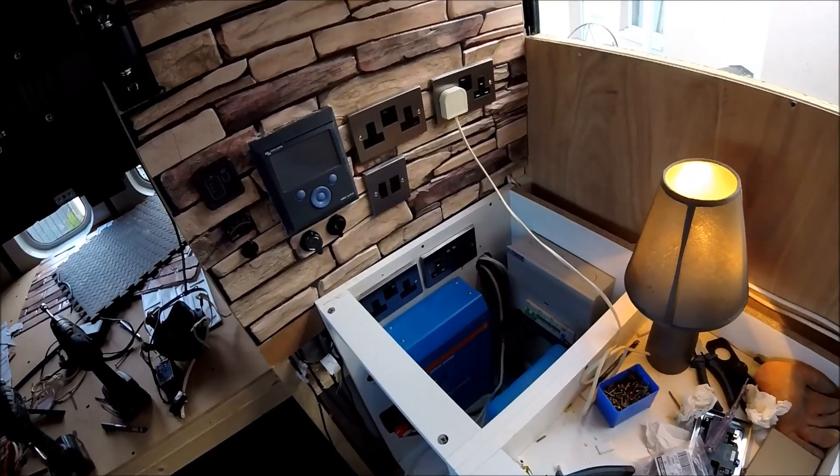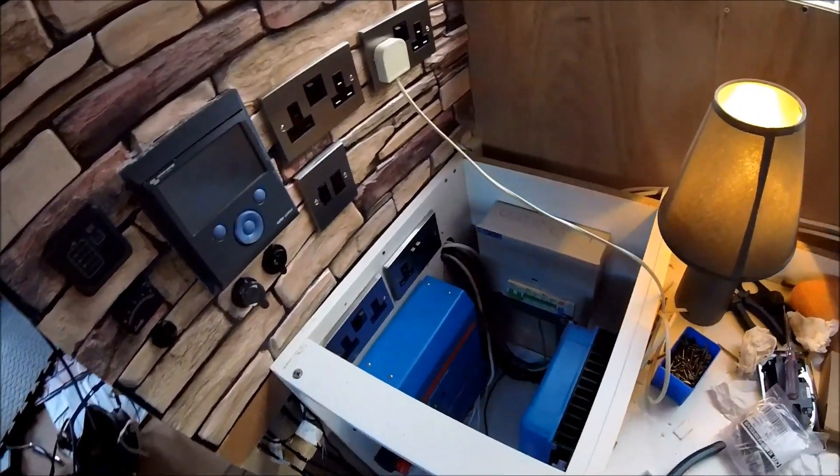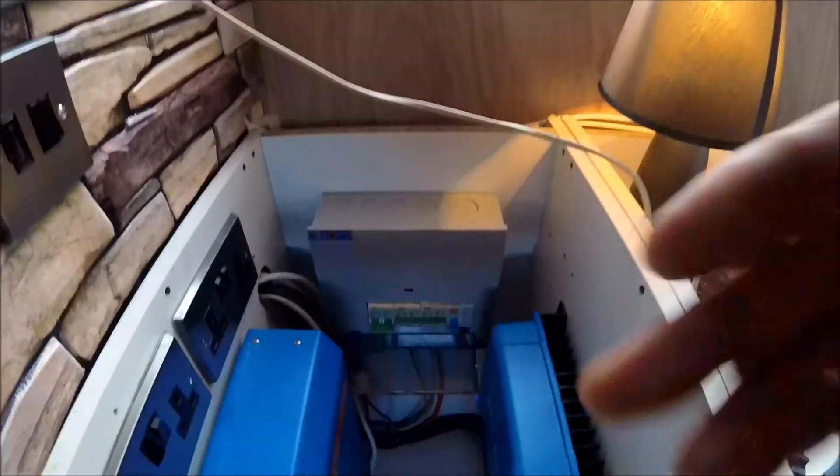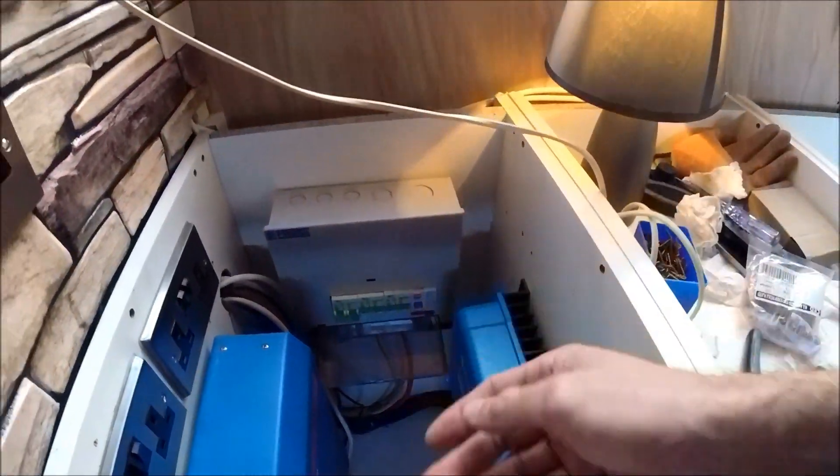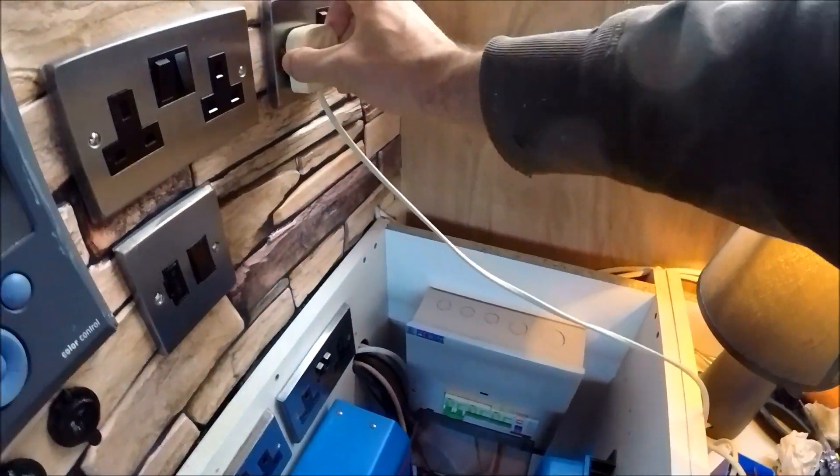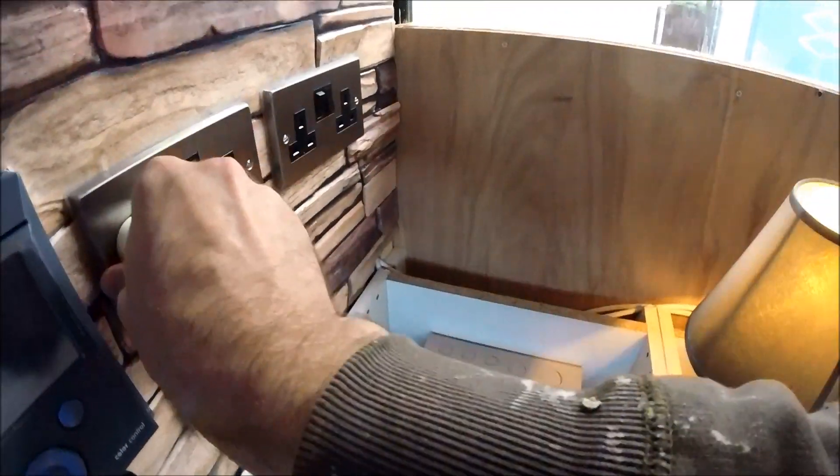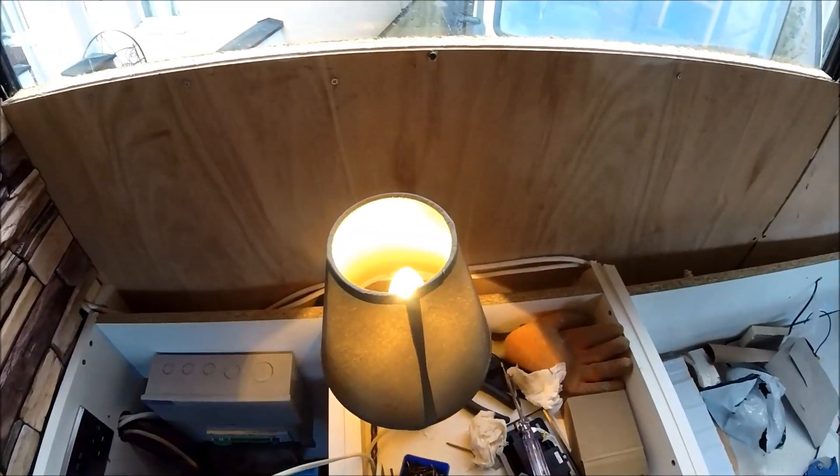Just reset the RCD and plug it back in onto the hookup point and that's working again there as well. So that's how I've fitted my 240 volt hookup point into a metal clad lined distribution box fed by RCD and dual pole MCBs.